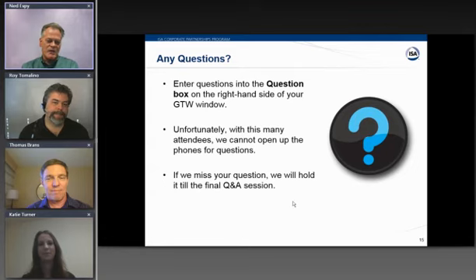Yeah, I'm not a pure mathematician or statistician in my explanation, but when you're looking at loop error, you just want to be in the ballpark and have some confidence. So RMS, or root sum square, isn't the end-all way. It's just one way to analyze the potential error. With my root sum square example, I'm just assuming that the transmitter might drift a little high, the probe might drift a little south. If they're all drifting in different directions, you might have zero error at the end of the loop.